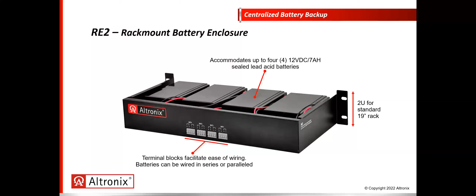One of the things I mentioned earlier that the Netway 4BT and 8BT have is our LINQ technology. With LINQ, we can control, monitor, and report power diagnostics from anywhere. We can see the battery health, manage multiple devices at multiple sites with our dashboard software, and report system diagnostics via email or our LINQ dashboard. We can control the outputs and reset devices if necessary. There's an event log that tracks the history of what's going on inside the unit. We can see the unit temperature, and we can also monitor the inputs and outputs of voltage and current for each individual output, depending on the device we're using LINQ with.